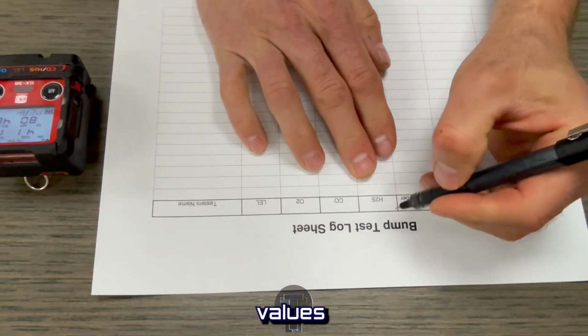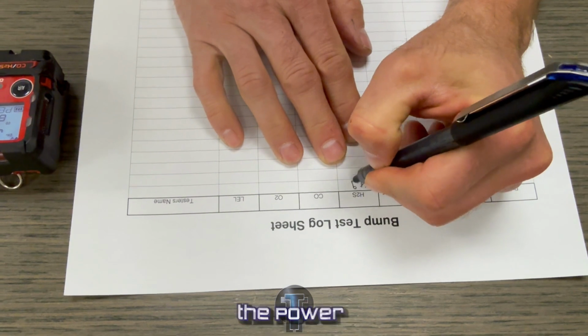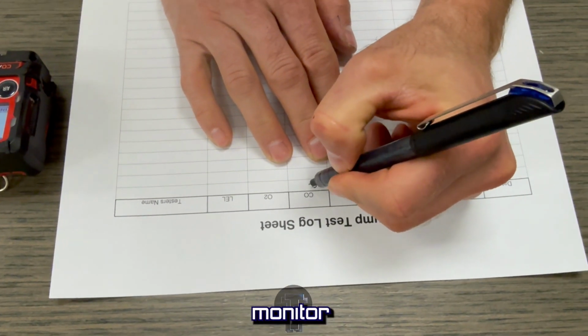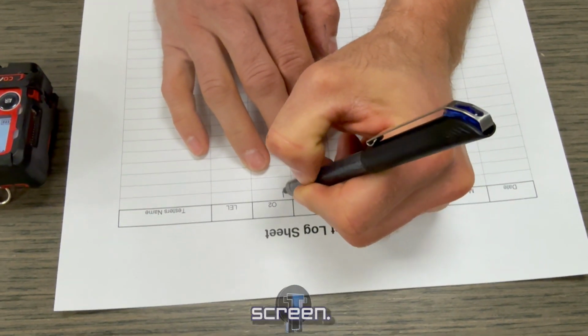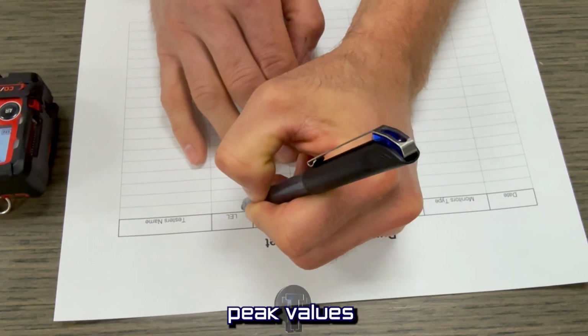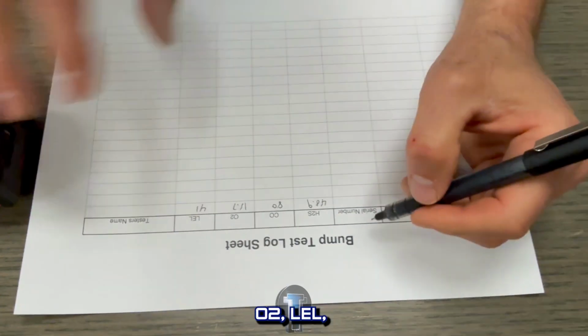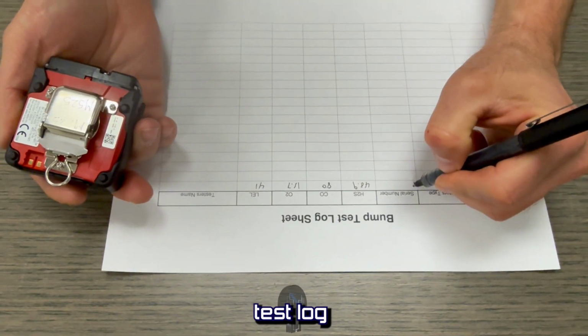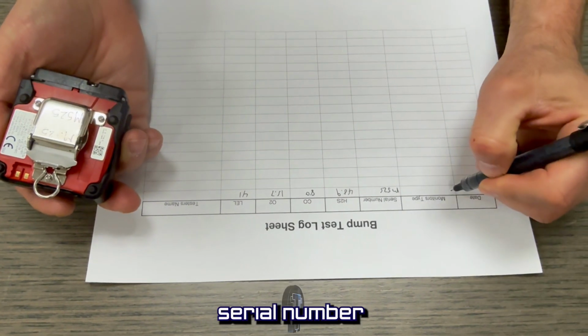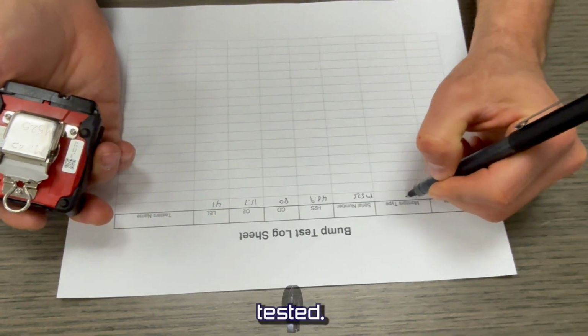Document the alarm values and complete the bump test record by pressing the power mode button on the personal gas monitor to cycle to the peak reading screen. Document the bump test peak values for H2S, O2, LEL and CO on the bump test log sheet with the date of the test and the serial number of each personal gas monitor tested.